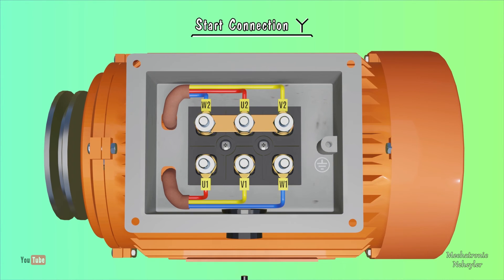The external line cables reach the three-phase motor box to connect to the corresponding terminals. Like the previous connection, L1 remains connected to terminal U1, L2 remains connected to terminal V1, and L3 to terminal W1.